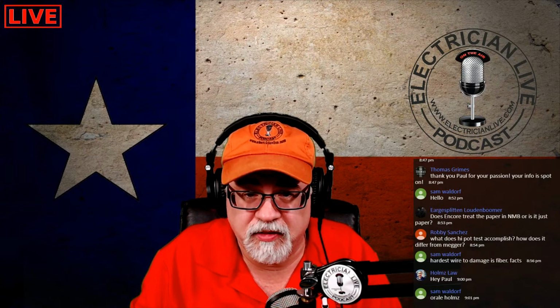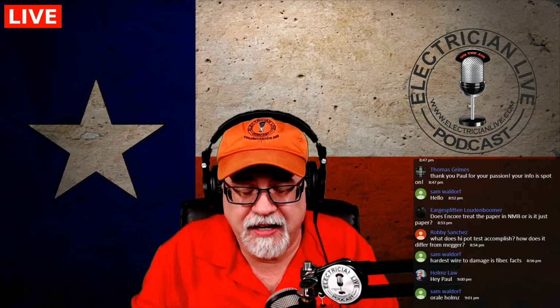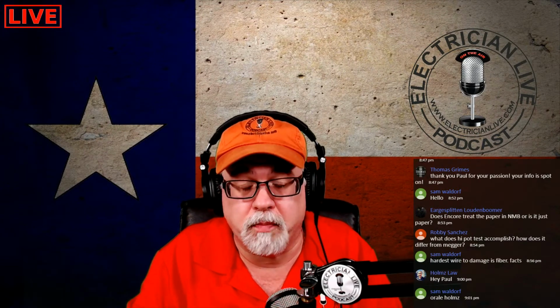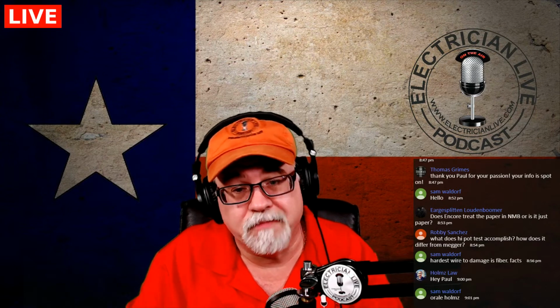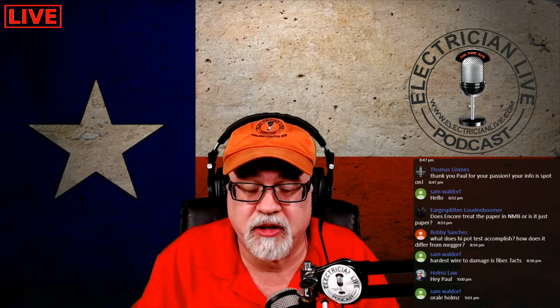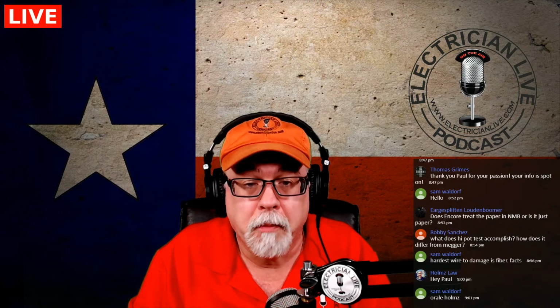It's usually going to take whatever the rating voltage is that you've got. It's that times 2 plus 1,000. Okay, so if it's 600 volt rated insulation, it'd be 600 times 2 plus 1,000. So we typically would be 2,200 volts, as that's what we would put in there for a high pot test.